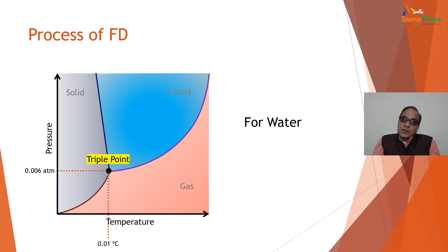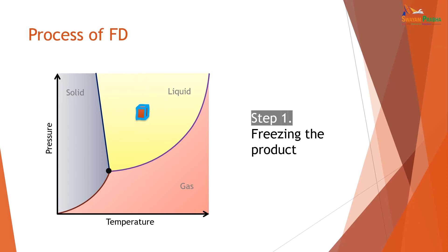For example, when we are talking about freezing the product, we decrease the temperature to freeze it from liquid to solid. As you can see in this inset video, the product is being frozen by decreasing the temperature. The liquid is slowly being frozen. Some part of this freezing must be done in the pre-freezer, in the normal refrigerator. Always remember this technical point: at the time you start the freeze drying, the temperature should already have been reached. If the recommended operating condition is -40 degrees, then -40 degrees should already be there when you introduce the pre-frozen product. It requires almost 2 to 3 hours sometimes, and it depends on the equipment for reaching that particular temperature.